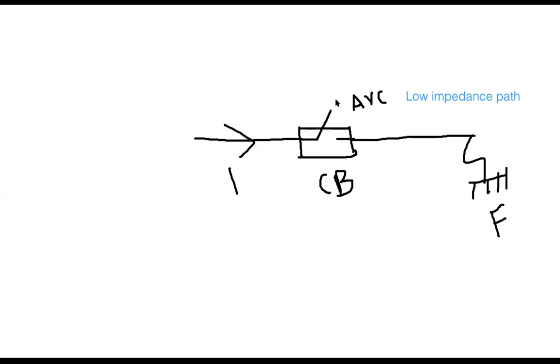Now the arc is going on. Arc means this type of connection; it is present. Let's say the prescribed time is that after opening the breaker, within 1 second you have to close the breaker, and the circuit breaker got closed. It is automated. But you reclosed it and still the arc is there. Then that is a dangerous situation. Therefore, in real practice, before reclosing the breaker, it is checked whether the arc is still present or has been extinguished.